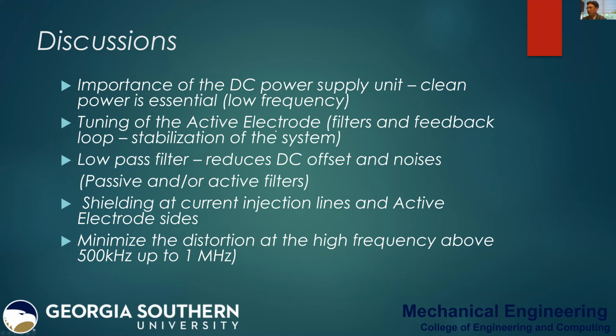Tuning the active electrode with low pass filters and feedback, by placing a resistor and capacitor in the feedback loop, is very essential, because the unity active electrode is very unstable. We have to eliminate unwanted noise, and the low pass filter helps minimize DC offset and noise.